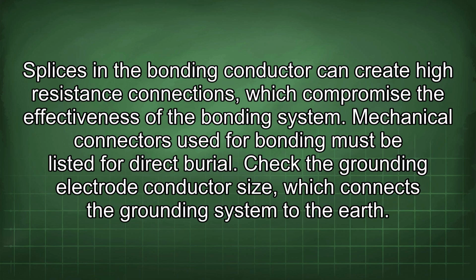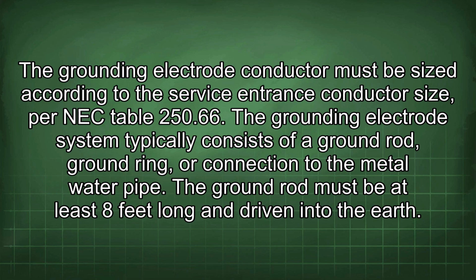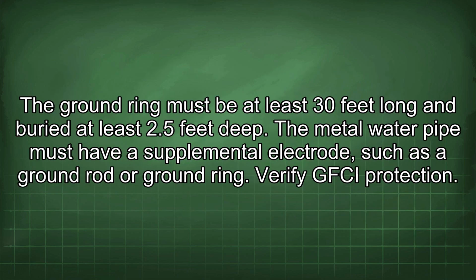Check the grounding electrode conductor size, which connects the grounding system to the earth. The grounding electrode conductor must be sized according to the service entrance conductor size per NEC table 250.66. The grounding electrode system typically consists of a ground rod, ground ring, or connection to the metal water pipe. The ground rod must be at least 8 feet long and driven into the earth. The ground ring must be at least 30 feet long and buried at least 2.5 feet deep. The metal water pipe must have a supplemental electrode, such as a ground rod or ground ring.